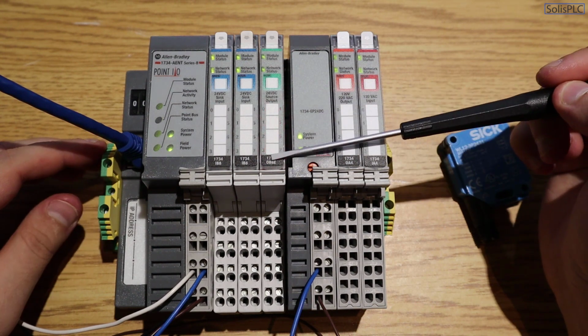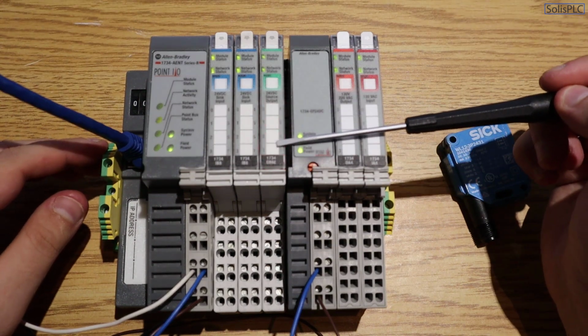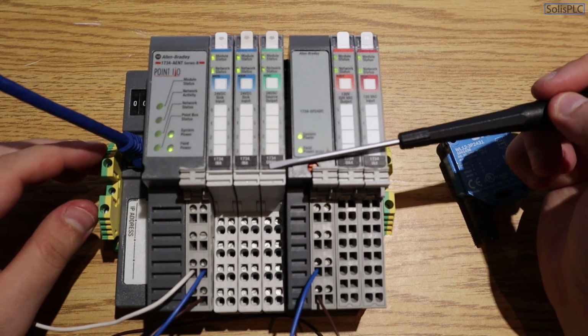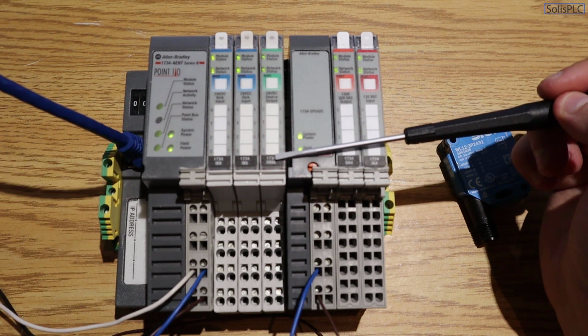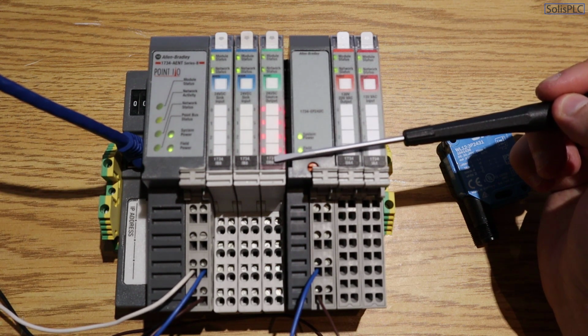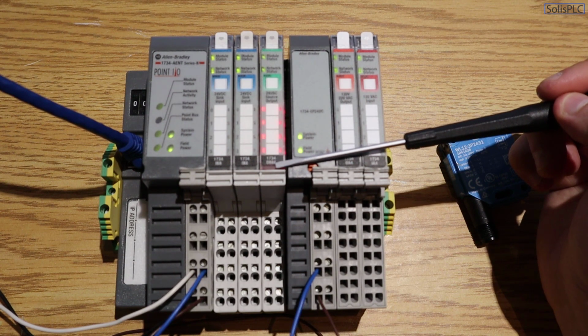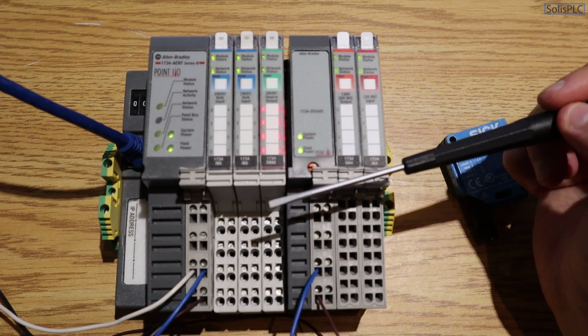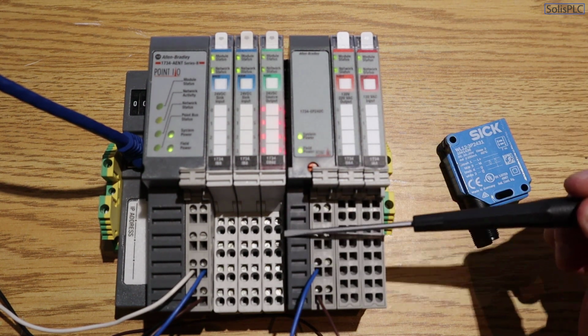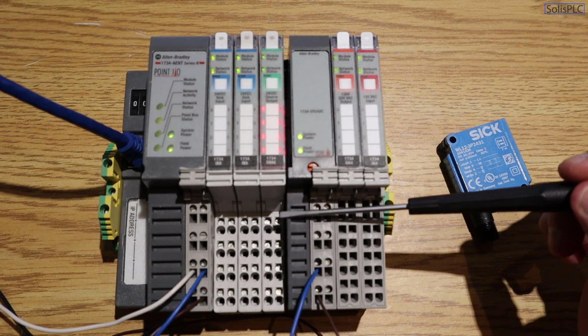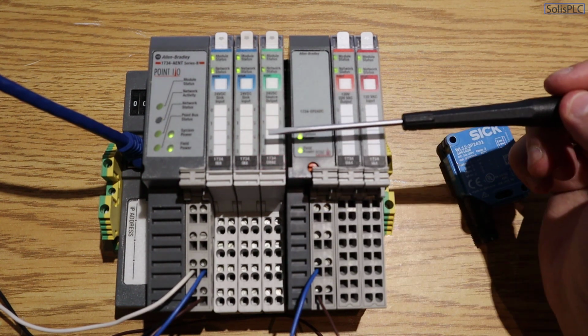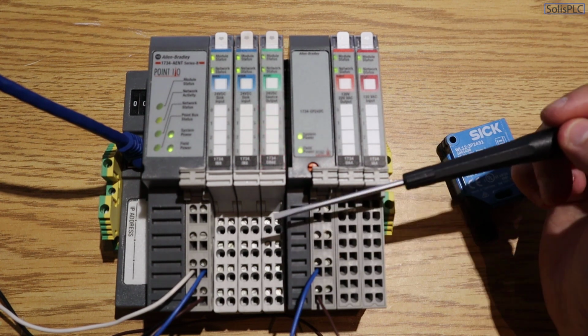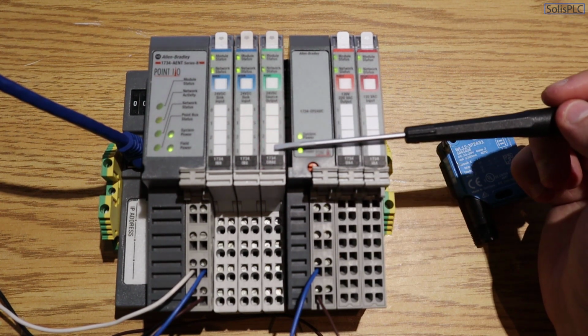In case you're wondering about this output module and the blinking red lights, this is essentially a specialty module, which is not only a direct output, but it also has diagnostics built in. So it's detecting that there's nothing plugged in. As you can see, there are zero wires on the output side, and it's detecting the simple fact that there's nothing plugged into the module. So this is not a major fault.